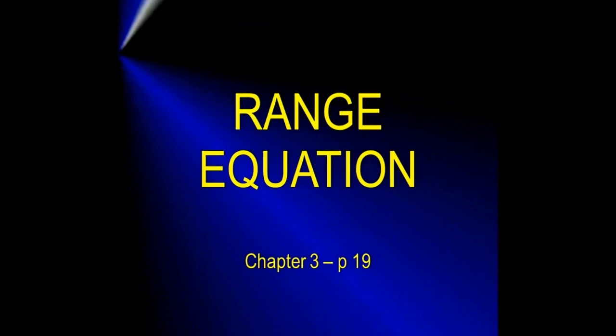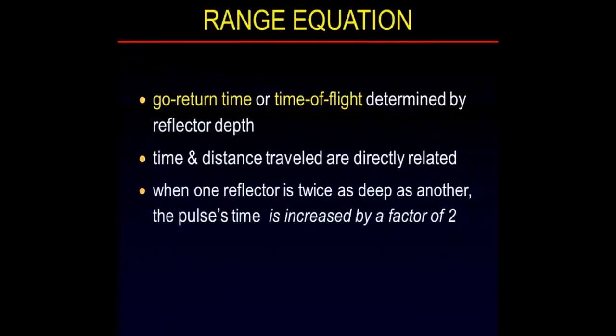Super important: the range equation. Ultrasound machines measure distance by the pulse's time of flight, or the go-return time. If a transducer sends out a pulse and a reflection comes back very, very fast, then the reflecting boundary is shallow. If the pulse takes much longer, then the reflector is deep, because the go-return time is directly related to how deep the reflector is.